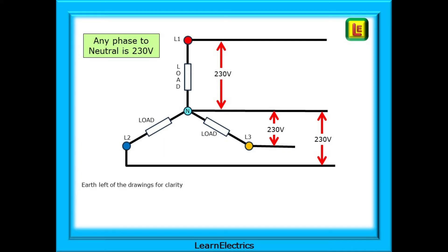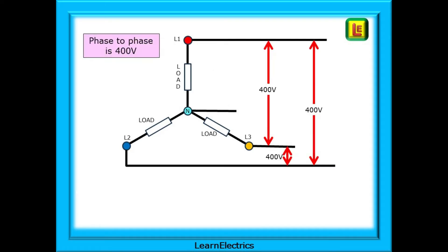A reminder then of the voltages available at a three-phase distribution board. Any phase to neutral is 230 volts nominal. Taking a phase from a breaker plus a neutral plus an earth will give you a single phase supply for a circuit, and any phase measured to earth or CPC is also 230 volts. If we measure phase to phase we will have 400 volts. L1 to L2, L1 to L3, and L2 to L3 will all be 400 volts.